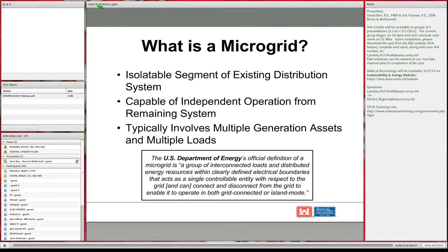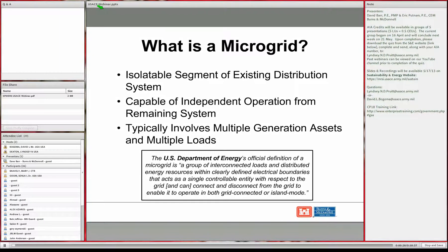A microgrid may be a section of a base installation involving one or more feeders that can be isolated from the rest of the distribution, or it could be an entire base that can be completely isolated from the utility system. By definition, a microgrid is capable of independent operations from the remaining system. If there are generation assets and loads within a microgrid boundary, they can operate with or without the utility and the rest of the distribution system.